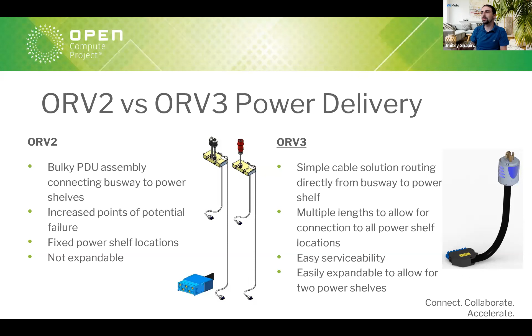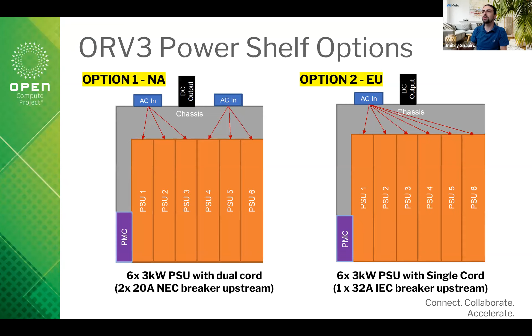Quick overview of the power shelves and why we have two different versions of cables. We have a North America power shelf and an EU power shelf. North America uses two 20 amp breakers, while EU uses one 32 amp breaker, leading to two different designs between the connectors and the overall cable itself.